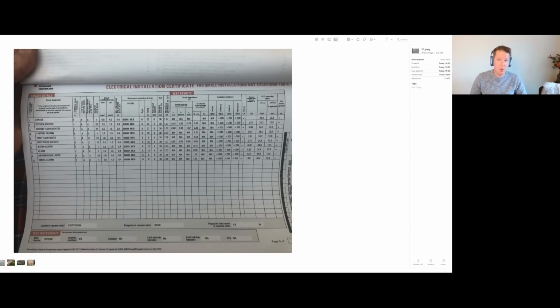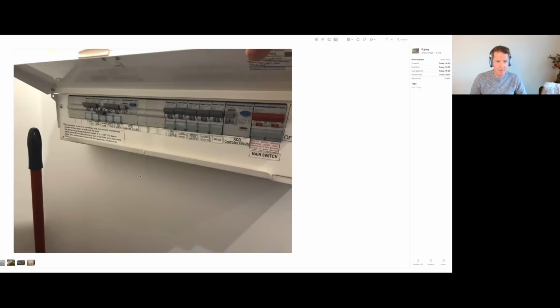So I asked the customer what would be the potential cable route from this house consumer unit, which you can see here, to the garage for the electric vehicle charging point. And this is where it gets complicated, because this is right in the middle of the house, of course. So it would be a very long, complicated run through the house, either lifting floorboards or running cable surface mounted in trunking through the house. Never ideal. And we don't have a non-RCD way that we can come off here either, so we'd have to rejig this consumer unit. Complicated.